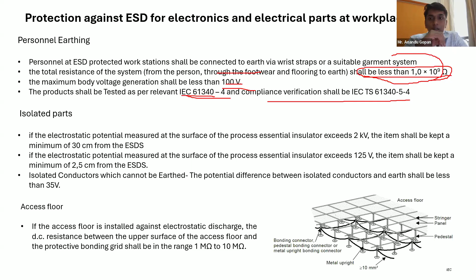If you have any isolated conductors which cannot be earthed, these conductors must have a potential difference of less than 35 volts. I'm not talking about your live conductors or anything like that. An isolated conductor, maybe for some electronic equipment or some process, which cannot be earthed - the potential difference between that isolated conductor and earth must be less than 35 volts. Strictly, I'm saying it again, it is not about the live conductors.